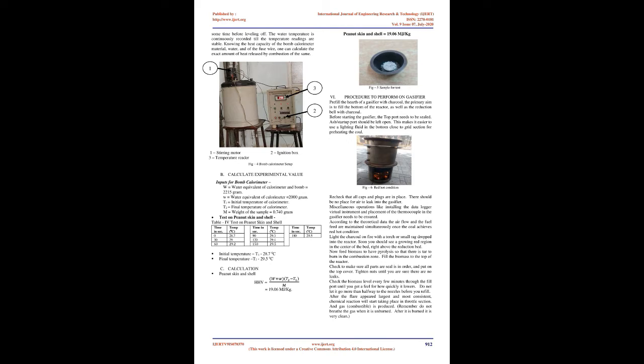Experiment on Gasifier Fuel Input: The higher heating value (HHV) can be measured in a bomb calorimeter using ASTM standard. A bomb calorimeter is a type of constant volume calorimeter used in measuring the heat of combustion of a particular reaction. In the bomb calorimeter system, the whole bomb, pressurized with pure oxygen and containing a weighed mass of sample, is submerged under a known volume of water in the bomb calorimeter vessel.